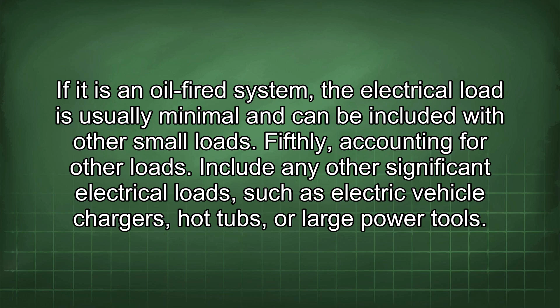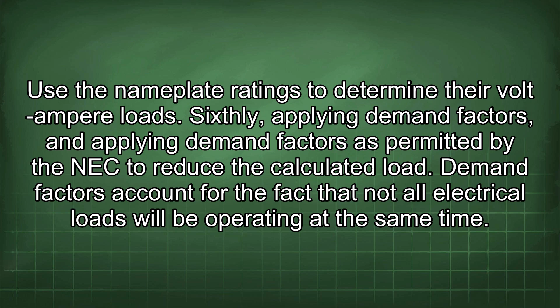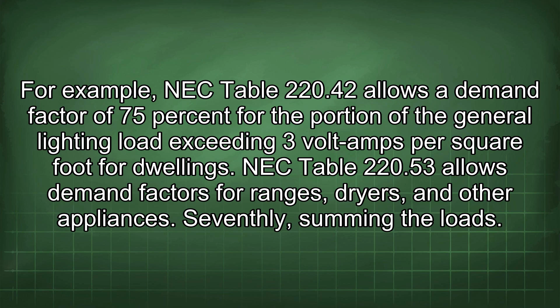Sixthly, applying demand factors as permitted by the NEC to reduce the calculated load. Demand factors account for the fact that not all electrical loads will be operating at the same time. For example, NEC table 220.42 allows a demand factor of 75% for the portion of the general lighting load exceeding 3 volt amps per square foot for dwellings. NEC table 220.53 allows demand factors for ranges, dryers, and other appliances.